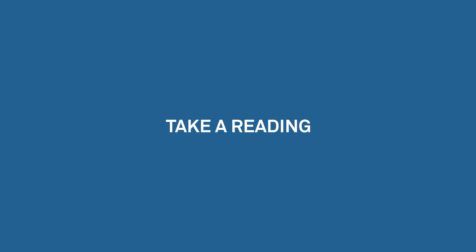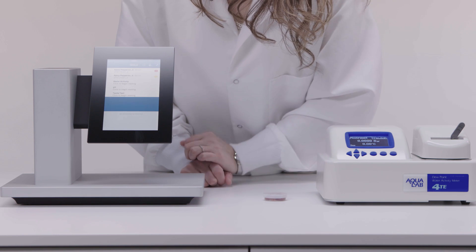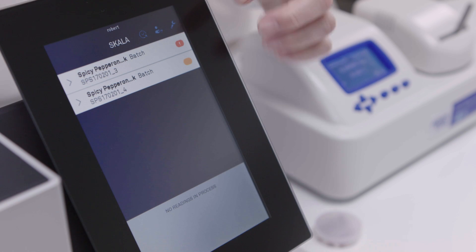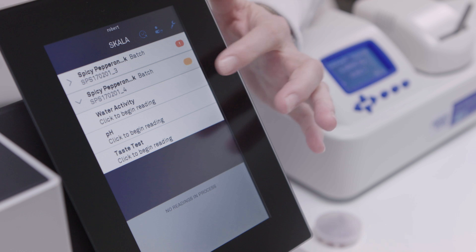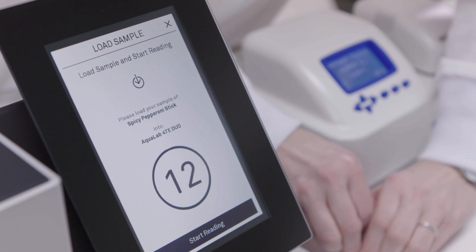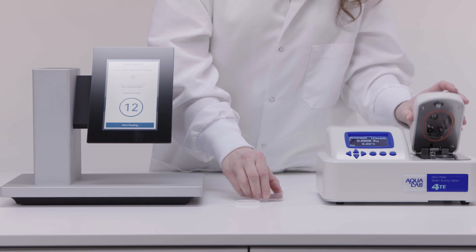Take the cup with your sample in it. We're going to designate the lot number for this sample in Skala, but you can do this manually also. Remove the lid if necessary and put the sample in the Aqualab. Close the top and slide the lever to read. Skala will listen for and record the reading, but you can also check the reading on the Aqualab screen.